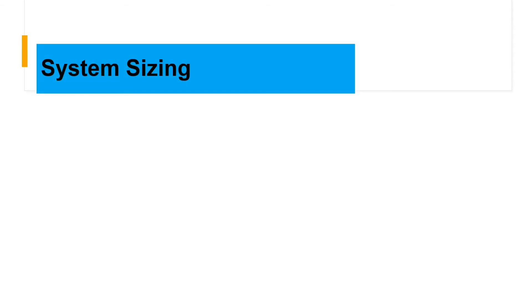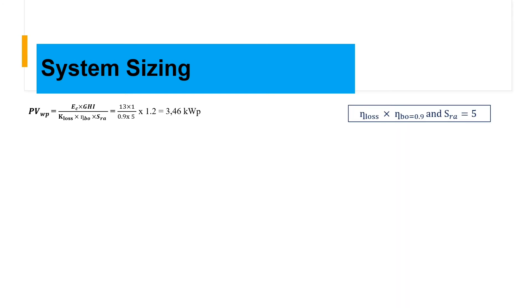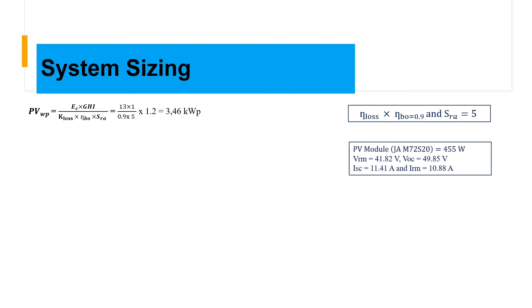Now let's size our system. For PV array sizing, we have an energy consumption of 13 kilowatt-hours, solar irradiation of 1 kilowatt-hour per meter square, losses, and solar radiation. The combination of all losses equals 0.9, and we have a solar radiation of 5 hours. This gives us a sized system of 3.46 kilowatt-peak, using a JAM72 S20 module.